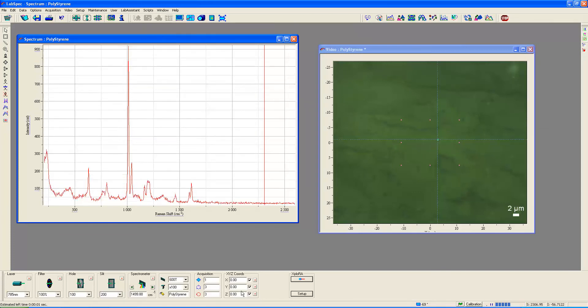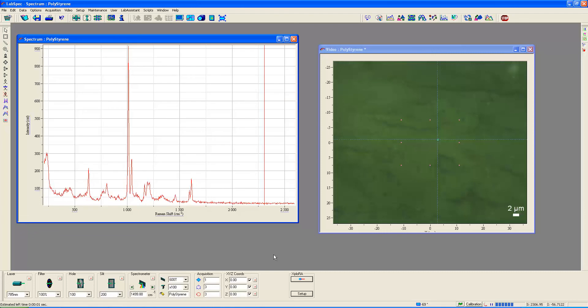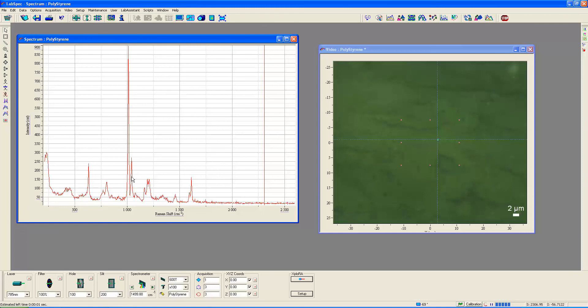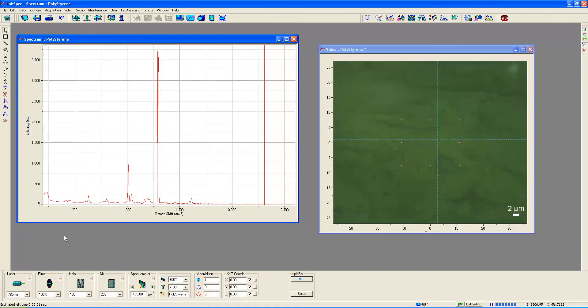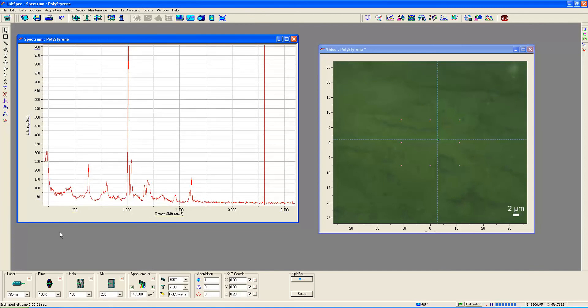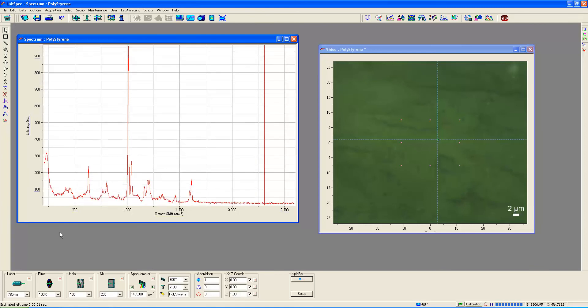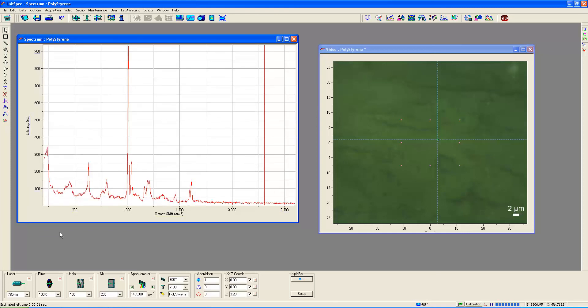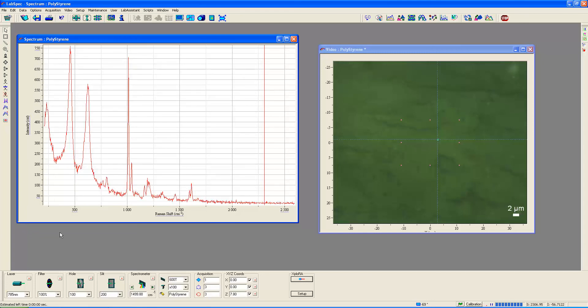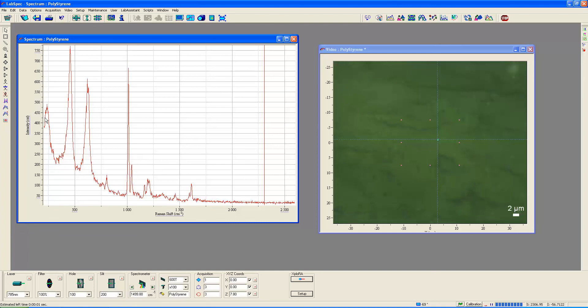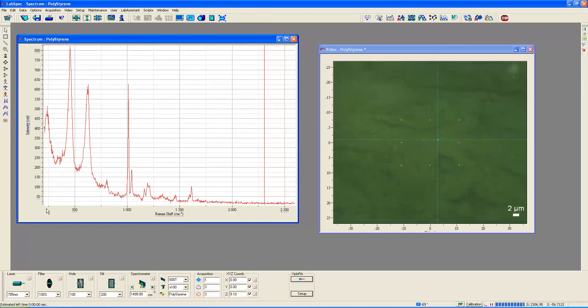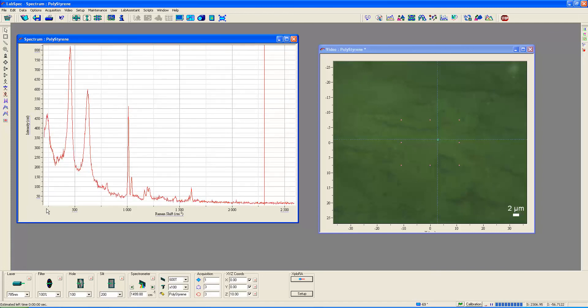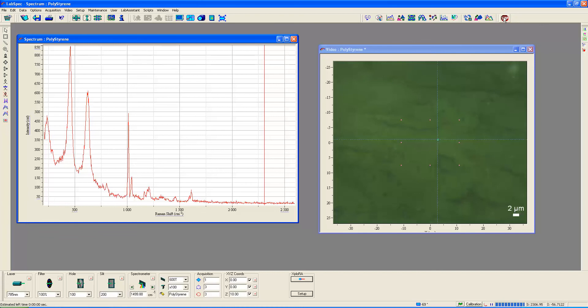Now what I'm going to be doing is I'm going to move the stage up. And as I move the stage up, I want you to notice the change in the spectrum that's going to appear right in this region, in the lower region below about 600 reciprocal centimeters or so. So now I'm moving the stage up. We're at about 2.3 micrometers or so. And I'm continuing to move the stage up. And notice, you see, look at these two very strong bands up here. And I'm going to keep moving the stage up until it reaches sort of a maximum. I just moved the stage up and you see now the appearance of these bands in here.